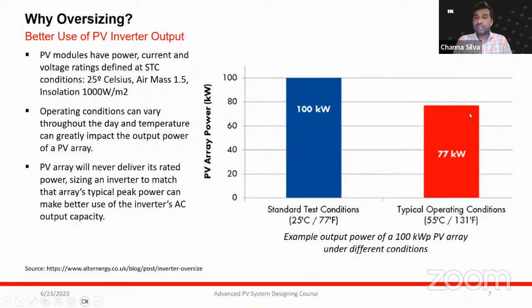In such a situation, what is going to happen? It's derated because of the temperature coefficient of voltage and power, so the power will be reduced by a certain degree. So in this case, comparing the standard test condition and the actual operating condition, 100 kilowatt reaches 77. It means 23% of the power will be reduced in actual terms. So if we want to select an inverter for this case, a 77 kilowatt inverter is more than enough to cater for the requirement.